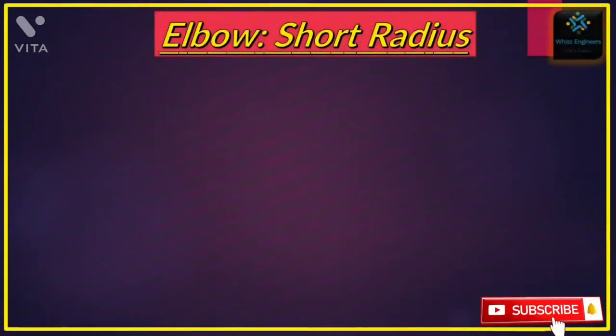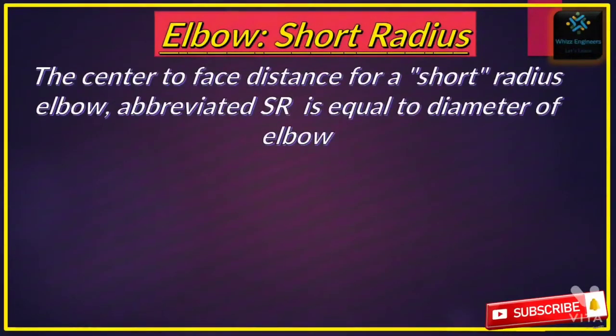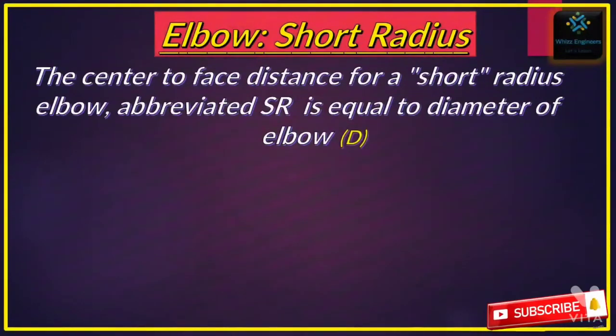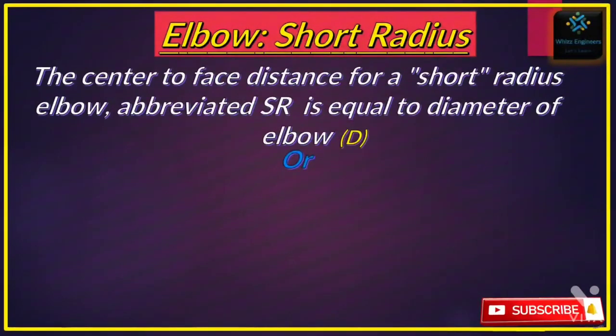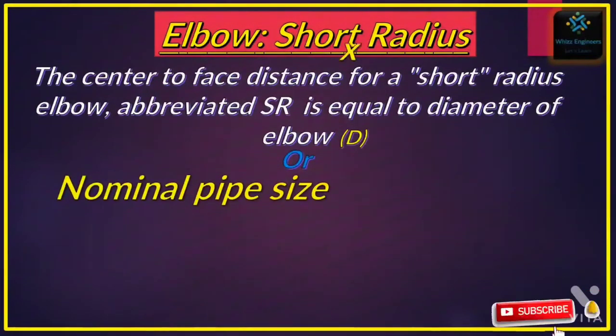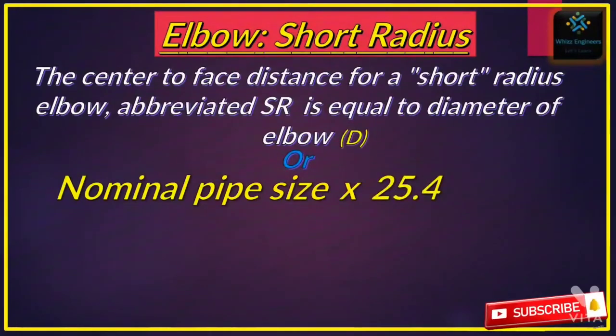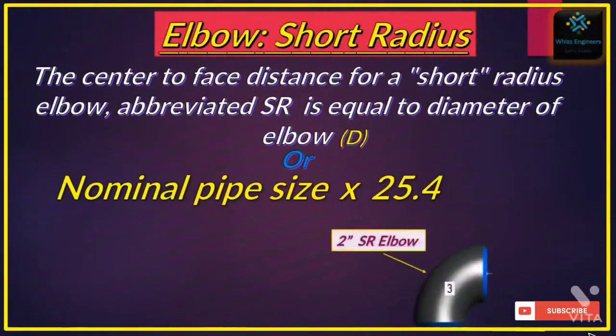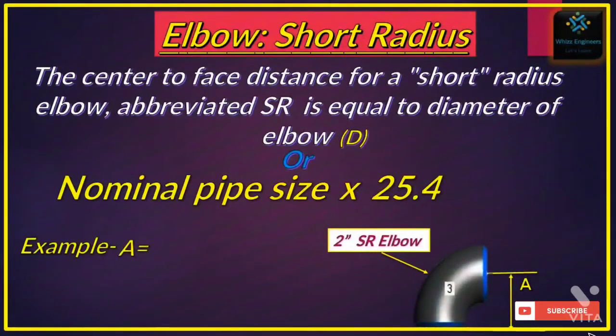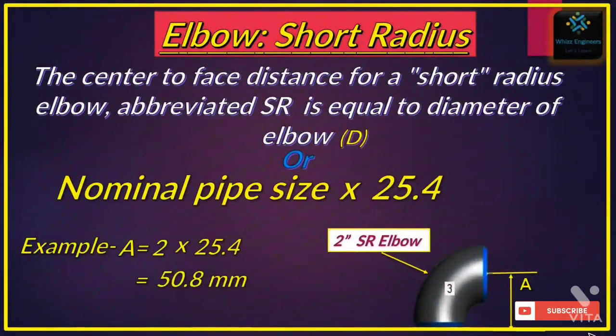Now we will see the short radius elbow. The center-to-face distance for a short radius elbow, abbreviated as SR, is equal to the diameter of the elbow. If you calculate it in mm, it will be nominal pipe size multiplied by 25.4. For example, for a 2-inch SR elbow, A is equal to 2 × 25.4, so A equals 50.8 mm.